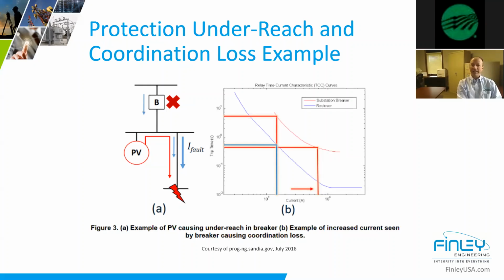And I'm noting in figure A there, an example of an underreach is the PV system, due to its ability to feed into the fault quickly before its protection scheme may enact, it's going to feed into that fault potentially, and it may not draw the same magnitude fault current through breaker B, basically meaning breaker B may not trip in a certain fault condition. We call that an underreach because it's not protecting in that case. If you have a low level magnitude fault, you have the potential that breaker B won't trip. And then you can see it from the curves there. Look at the potential, or you're going to go upstream and you're going to trip on a faster curve, or something that can handle a higher magnitude. And you can see the change in threshold current or the time to trip. That one's kind of an interesting one. A lot of people don't necessarily realize that potential exists.